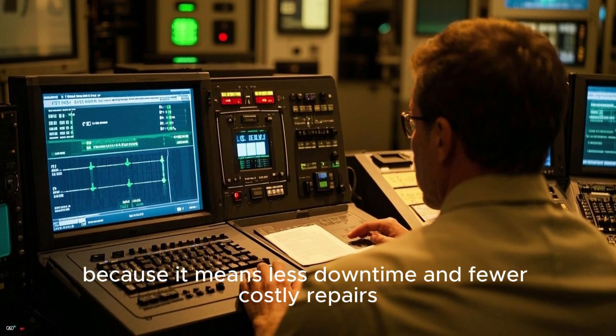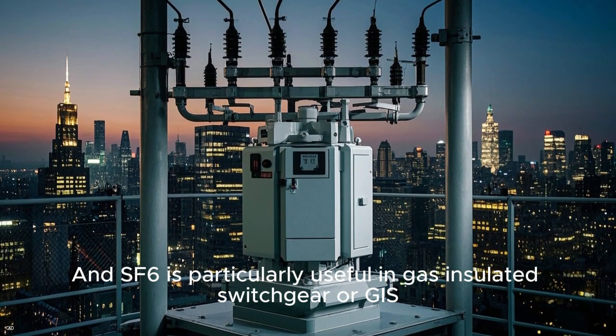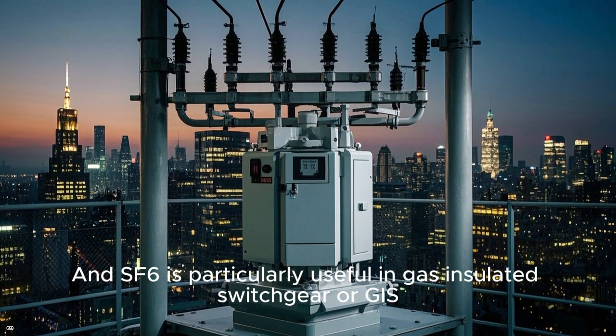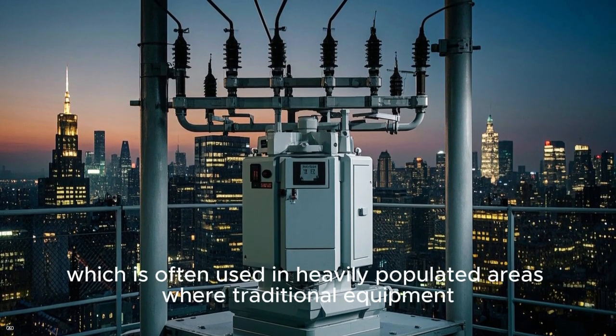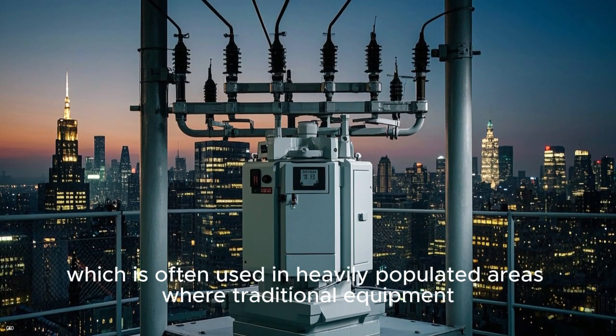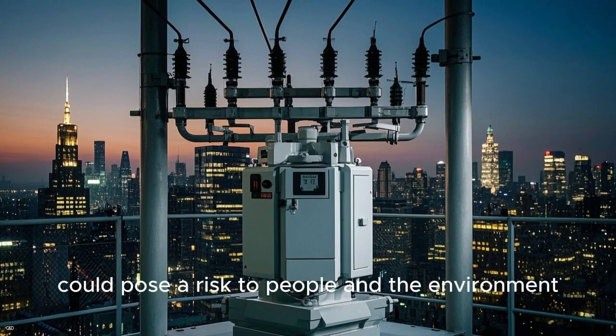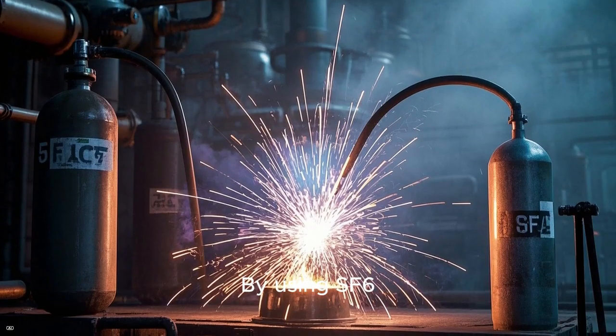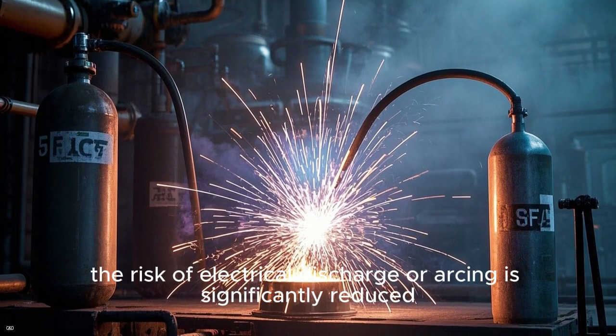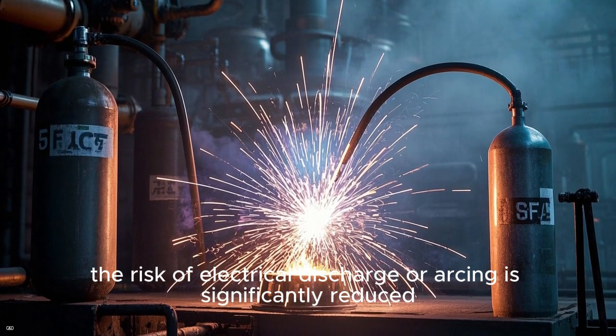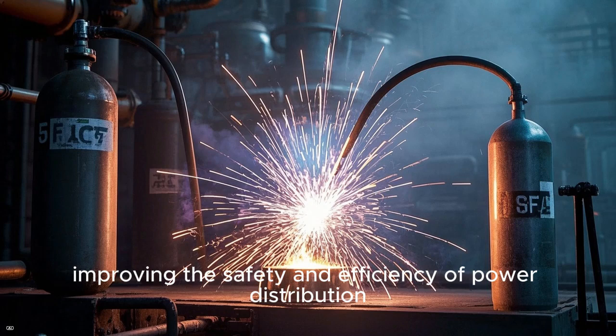SF₆ is particularly useful in gas-insulated switchgear, or GIS, which is often used in heavily populated areas where traditional equipment could pose a risk to people and the environment. By using SF₆, the risk of electrical discharge or arcing is significantly reduced, improving the safety and efficiency of power distribution.